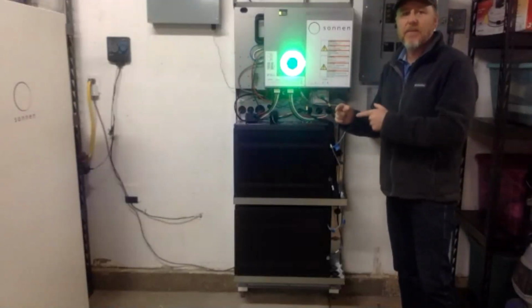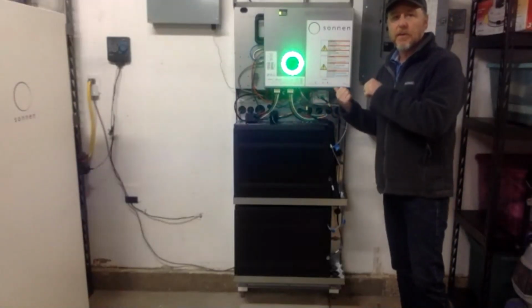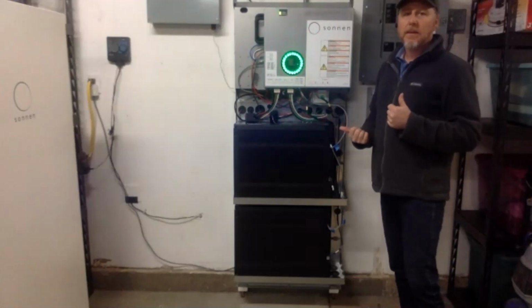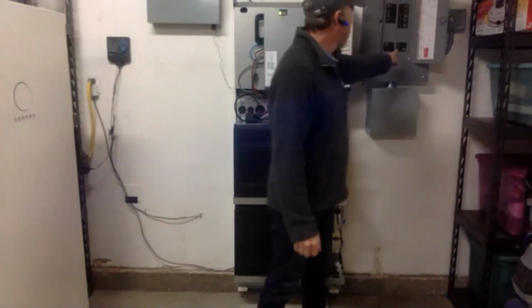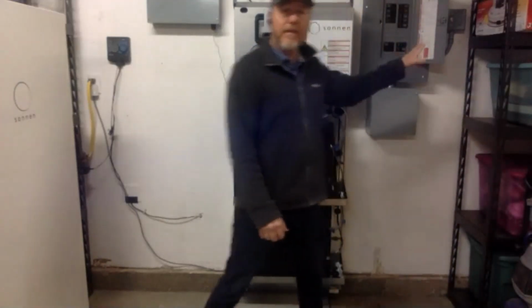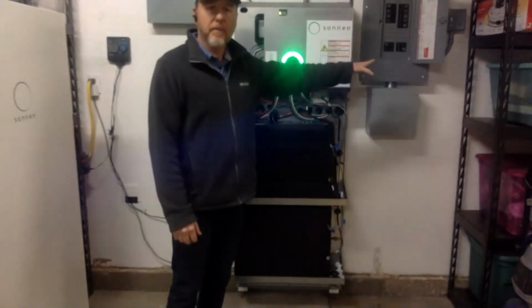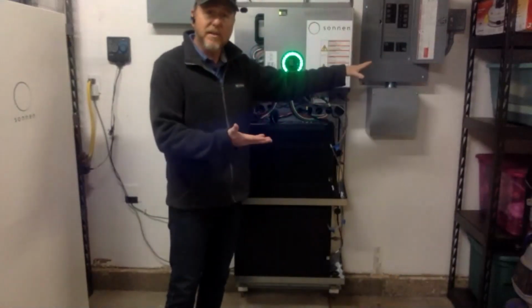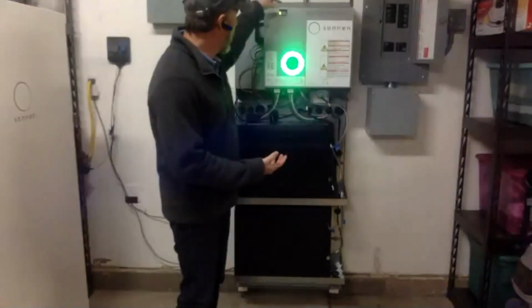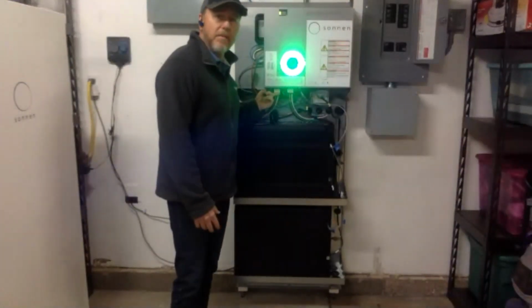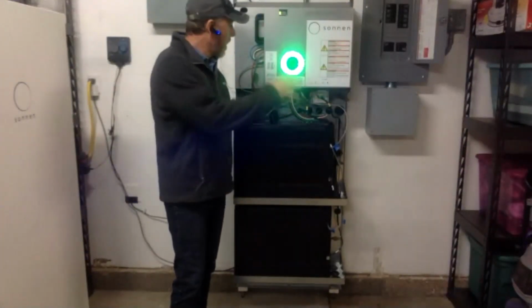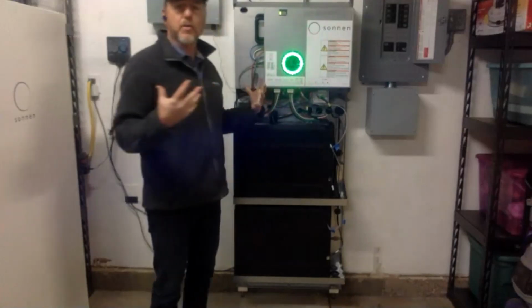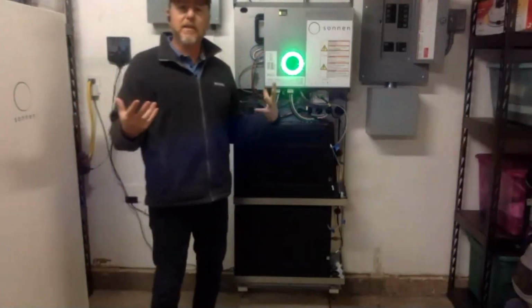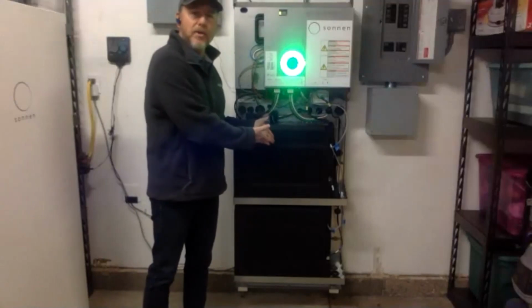You do not connect a PV array to this unit. We're AC coupled, so the solar over here feeds those loads first. And then if there's any excess solar, it goes up and over into the microgrid terminal, and the system will say, oh sweet, I got some excess solar, let me charge the batteries.